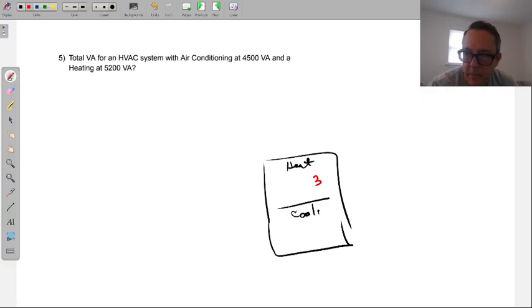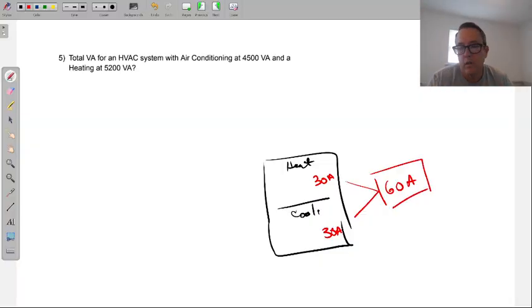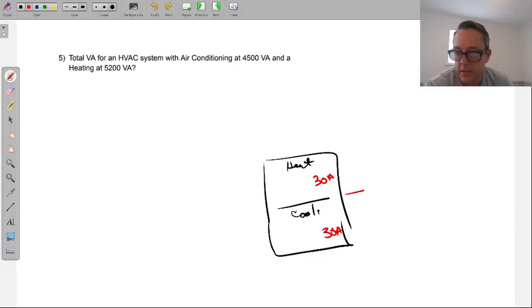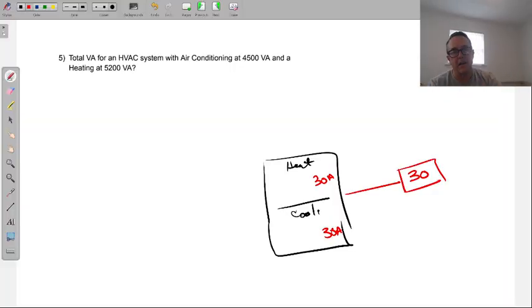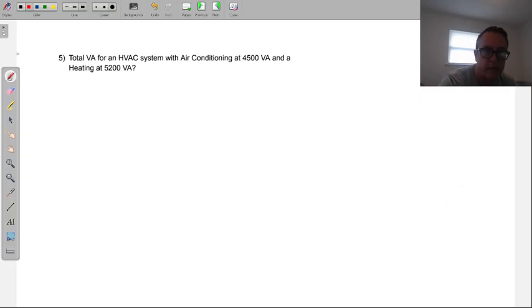For example, you'll see something like 30 amps here, and you'll see 30 amps here. What we are not going to do is say, all right, I must need a 60 amp breaker because I have a heater that's 30 amps and the cooling system is 30 amps. Instead, all we need is just a 30 amp breaker. That's all we need, because the heat and the cooling are never going to be on at the same time. The system is designed that way, to not run both at the same time. So it'll always be this way.